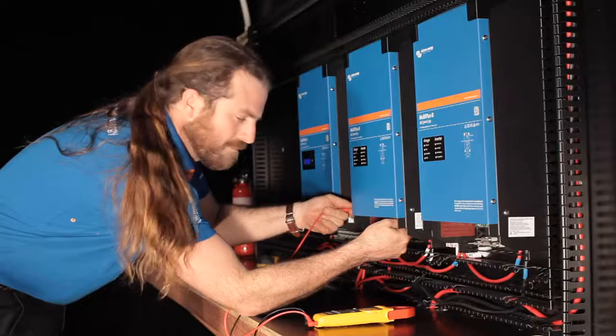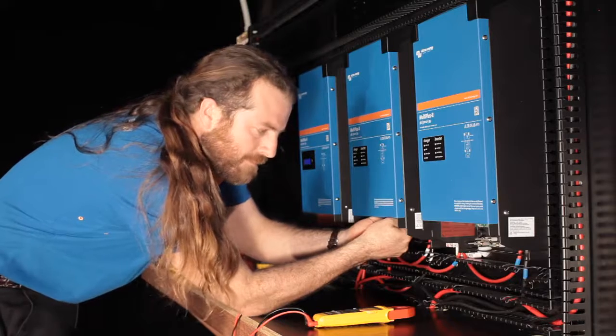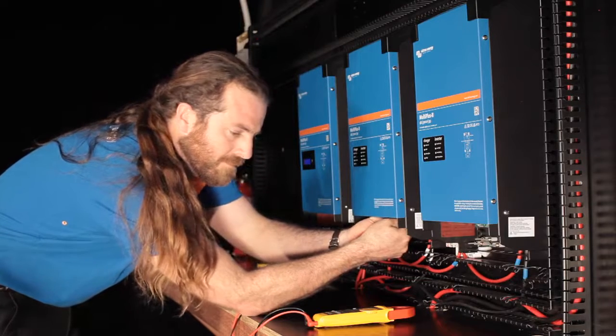This is critically important. Incorrect polarity at the Multi-Plus 2 can destroy the unit and is not covered by warranty. So take the time to check and observe correct polarity and voltage at each Multi-Plus 2 before closing the isolator and switching it on.